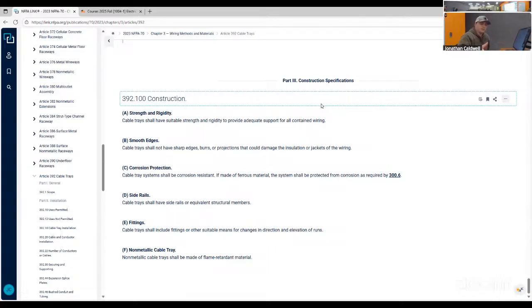So how we support our tray, they have clamps essentially. They're just plastic clamps or fiberglass clamps, I can't remember which. But we drill through the angle iron and then we just clamp it like that. It's typically how we do it. For your answer, no, that is technically not grounded because you're putting a plastic clamp onto our tray. And at the same time, our tray technically does not need to be grounded because it's fiberglass, right?